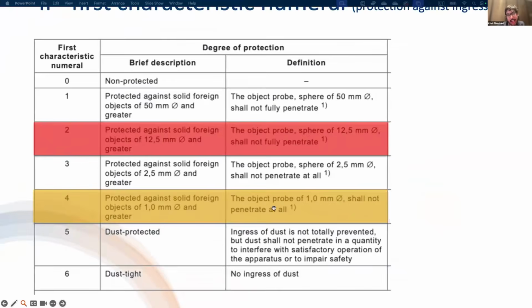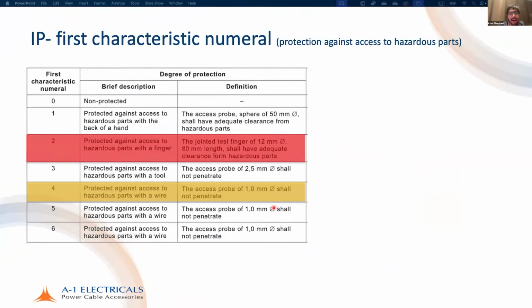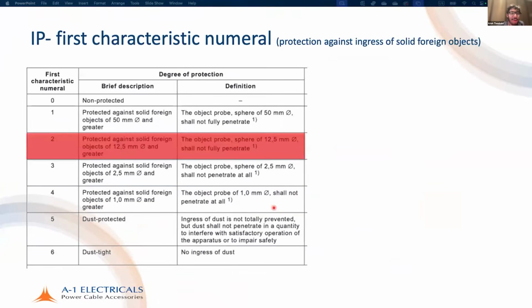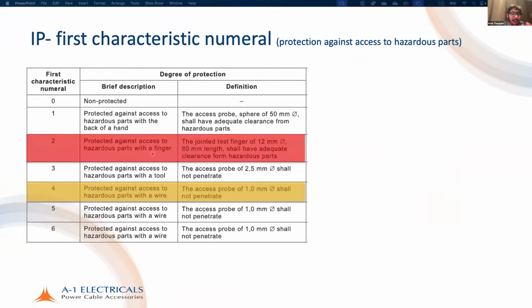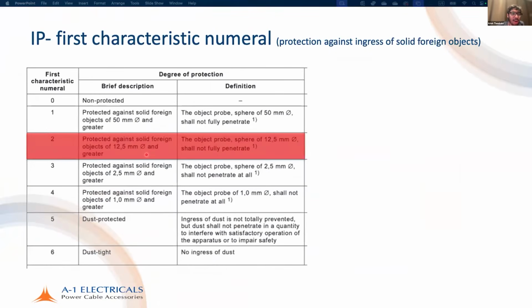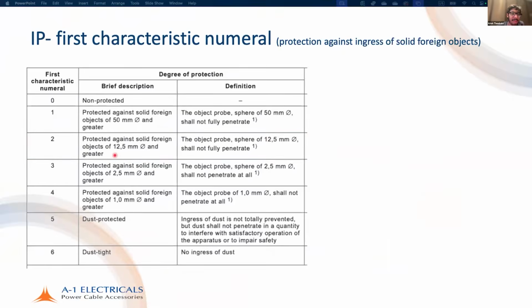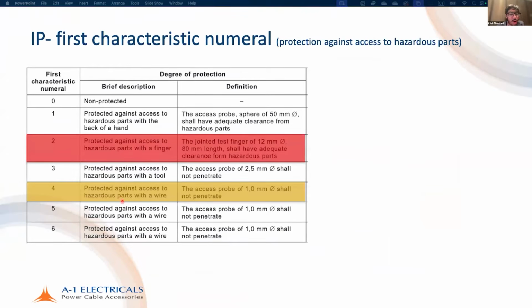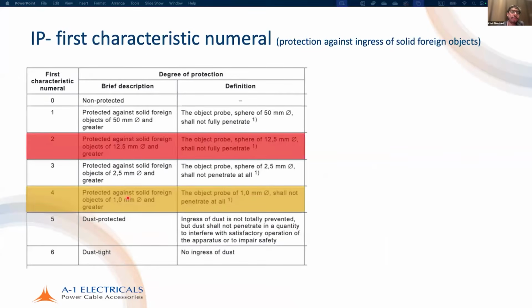Very important, right? The first characteristic numeral identifies both of these. So if it's IP2X, the finger is protected against, and solid foreign objects greater than 12.5 millimeter. If it's IP4X or just IP4, it is protected against access to hazardous parts with a wire, and an object greater than 1 mm diameter cannot penetrate. So this is the first characteristic numeral.